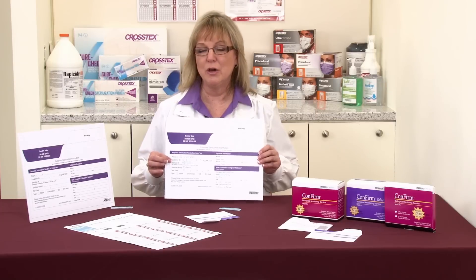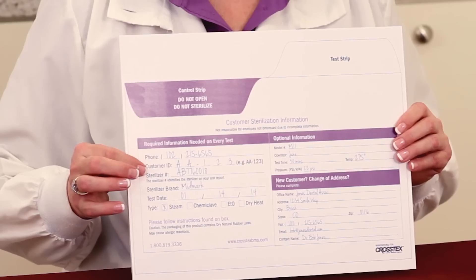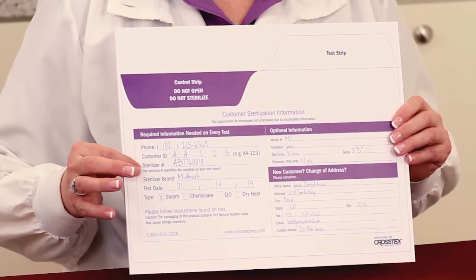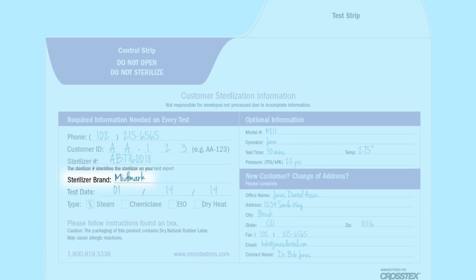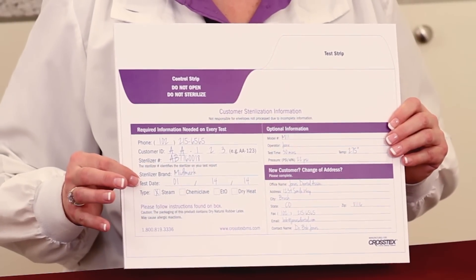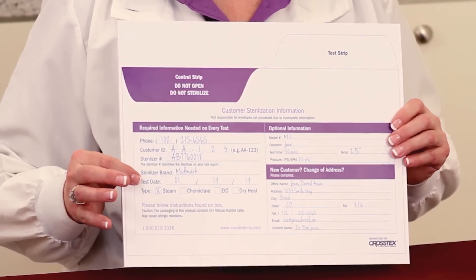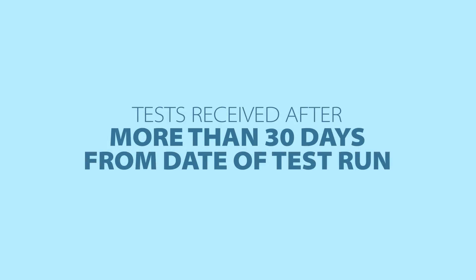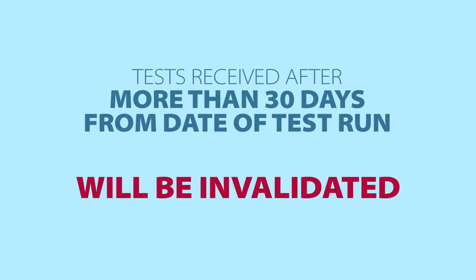Because we're an FDA-regulated facility, we have to enter the data exactly the way it's written on your test card. The next item is the sterilizer brand, whether it's a Midmark, a Pelton Crane, or a SciCan. The next key item is your test date — that's the date that you actually ran the test. We need to receive the test in the mail within a 30-day timeframe after the test has been run.